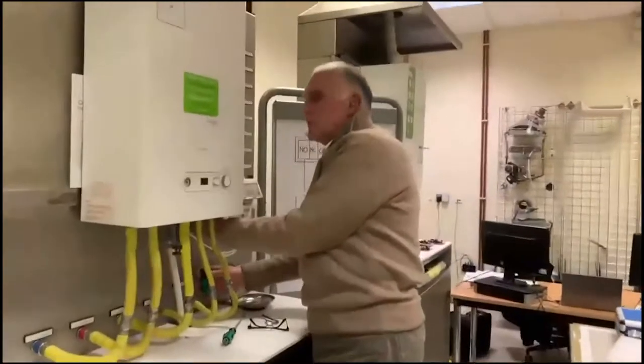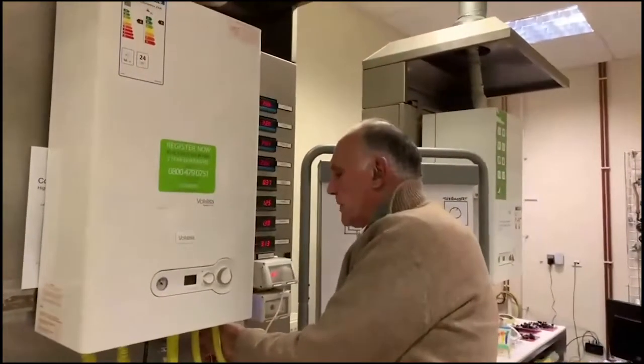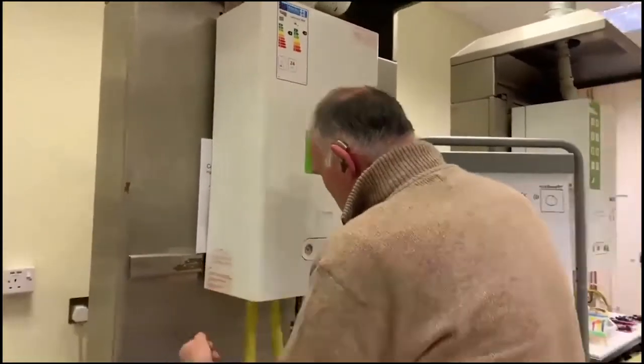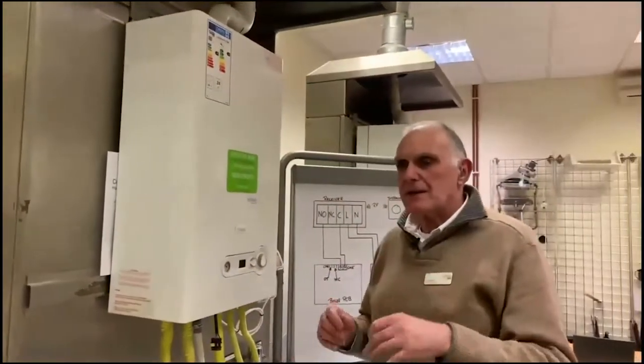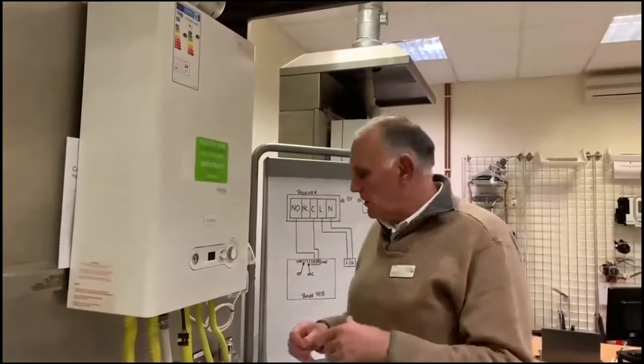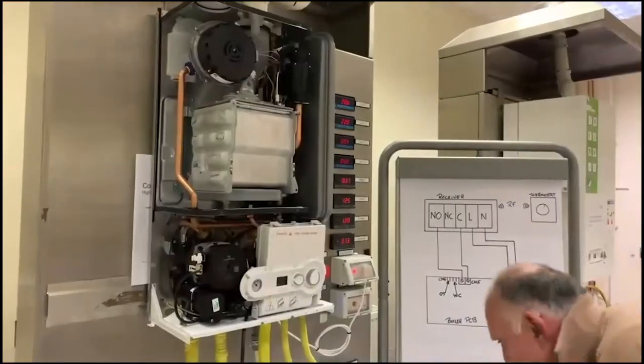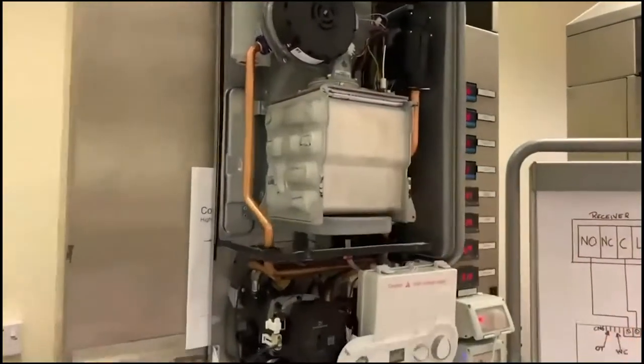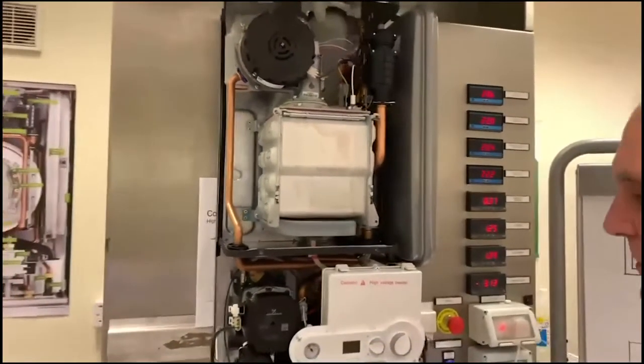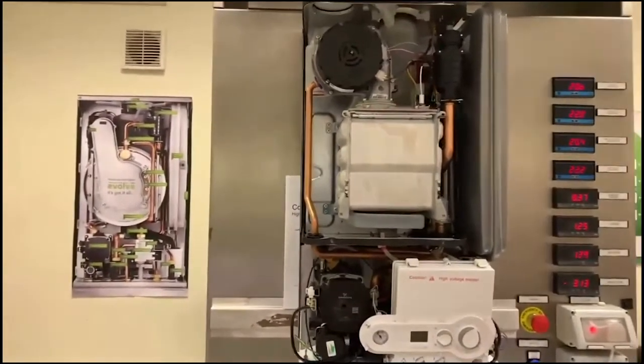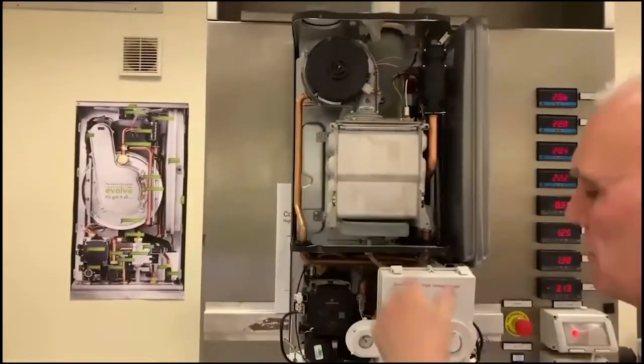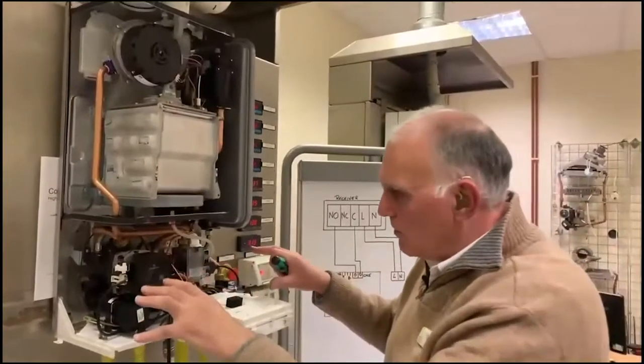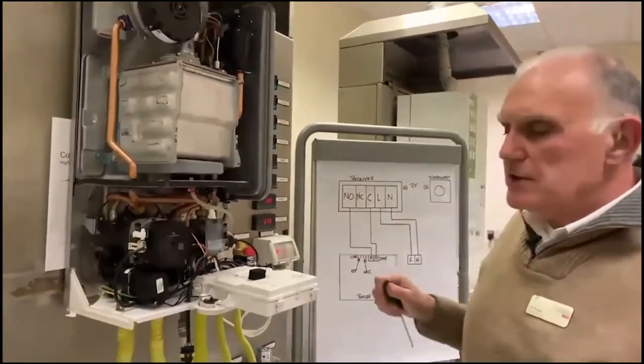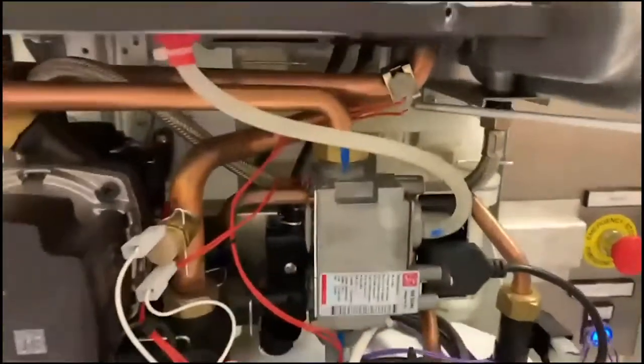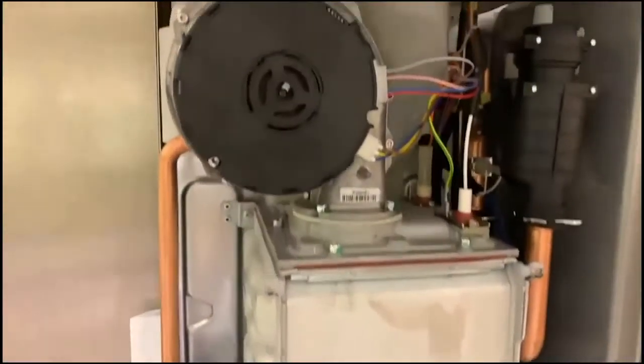This is the platform, which is the most popular, the Compact A, 25, 29, and in the Compact A, there's a 32 kilowatt model, 8-litre expansion vessel. This one has the 25 kilowatt heat exchanger. The larger heat exchanger is exactly the same, it's simply 40 mil wider. The same water block, same gas valve as the Vision Plus, same return thermistor, flue thermistor, flow thermistors, automatic air vent.